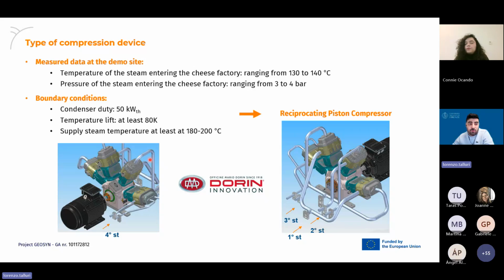The goal was to develop a heat pump with a condenser duty of 50 kilowatts, a temperature lift of at least 80 Kelvin, and a supply steam temperature of at least 180-200 degrees Celsius.